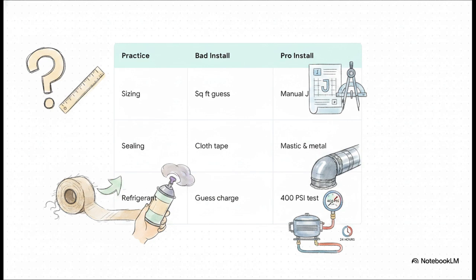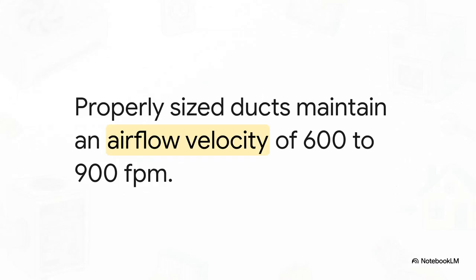A professional installer, complying with rigid Indiana mechanical codes for instance, will perform a 400 psi pressure test for a full 24 hours to ensure there are absolutely zero leaks before charging the system to factory specifications. A quality install definitely costs a bit more upfront, but it adds years to the equipment's life. It all comes down to precise standards, like Manual D for your ductwork.